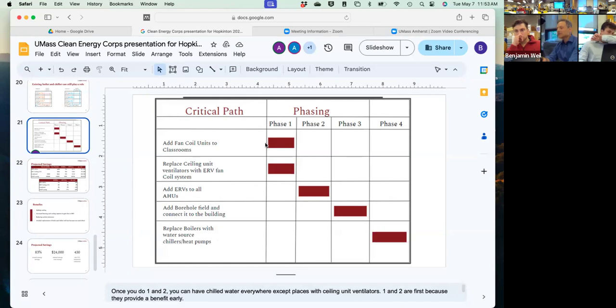That's a big deal. Adding fan coil units to classrooms could be really inexpensive. Basically, you're just adding capacity. You've got a supply and a return pipe that's going to a unit ventilator already. And this could be done classroom by classroom: shut off valve, cut into the pipe, add a connection and a balancing valve, right? Very, very simple. Probably $2,000 in parts, and then let's call it another $2,000 installed. So for 36 of the classrooms, let's just round it up to $5,000 per classroom.